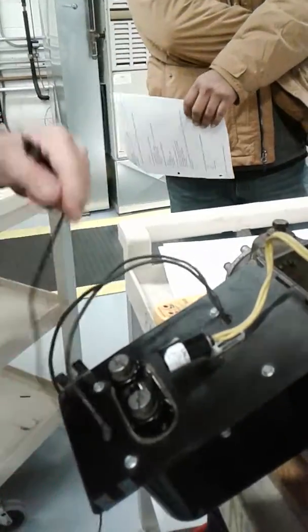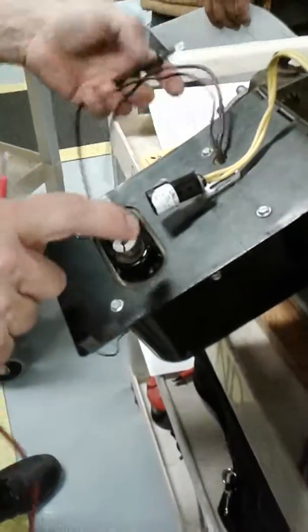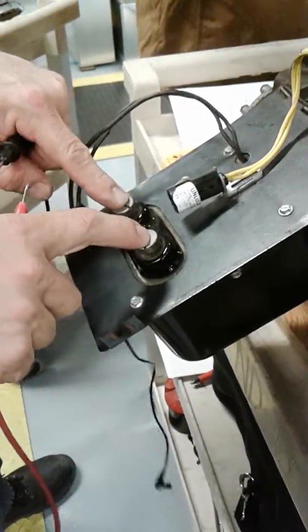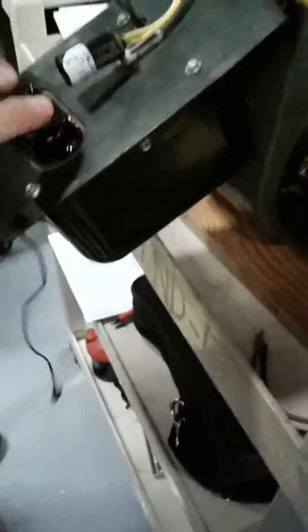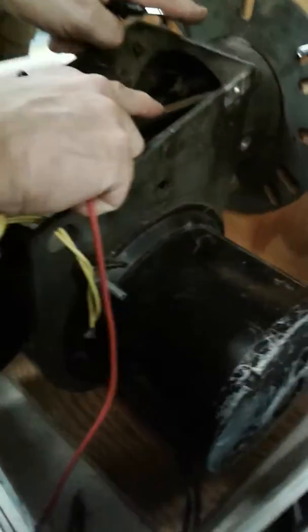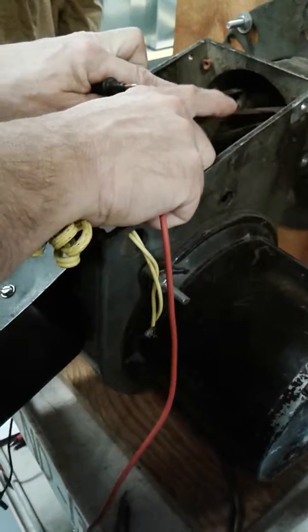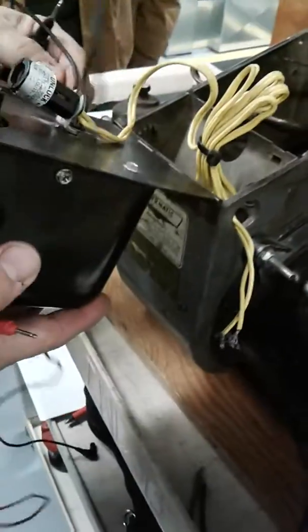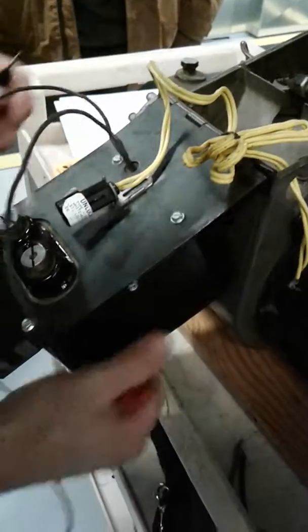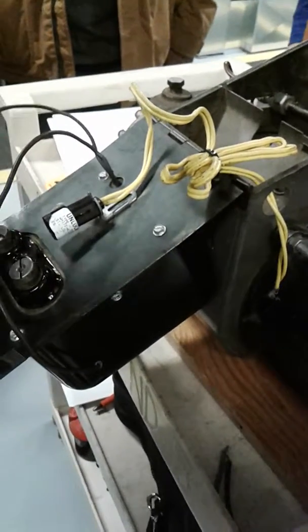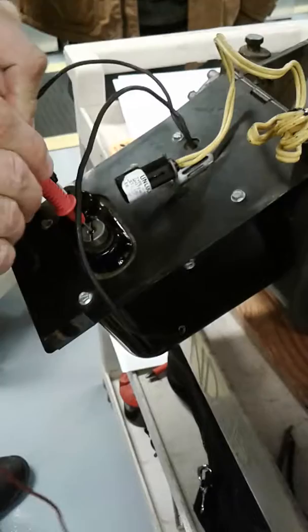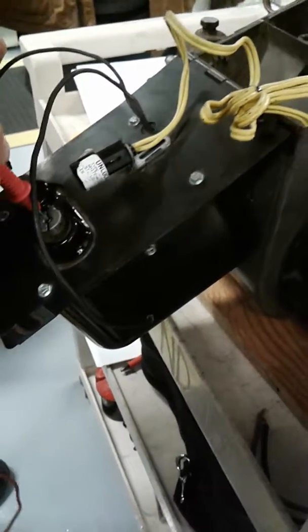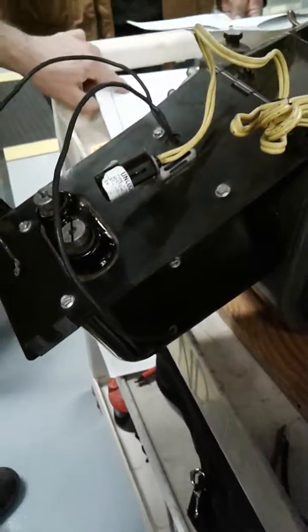So check it out, guys. This is the secondary side right here. This is where the 10,000 volts comes out. When you close this, these probes touch these here, which send the signal down through the electrodes, through the porcelain insulators, and create a spark in front of the nozzle. Okay? Like so. All right? Try not to pinch these wires too much in here. Okay? So, then you're going to write down the resistance by checking these two right here. And then you're going to read some type of resistance. Write it down. Okay? Next is letter D.